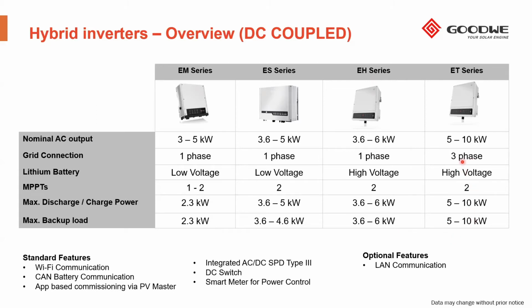Moving along to the 3-phase range, we have the ET series, which is available from 5 to 10 kilowatts. It's compatible with high voltage batteries. It also has 2 MPPTs, and it's available in 5, 6.5, 8, and 10 kilowatts. Its discharge and charge power is in line with its nominal output rating, from 5 to 10 kilowatts, and the backup load is 5 to 10 kilowatts. However, the 5 to 10 kilowatts is spread across the 3 phases. So for example, each phase can provide up to 3.3 kilowatts of power on a 10 kilowatt ET inverter.